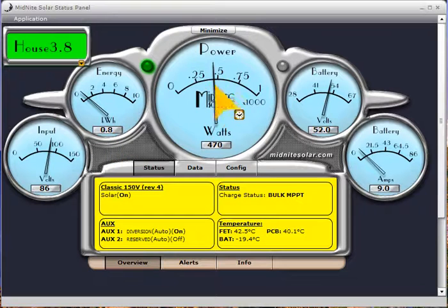And the next gauge is the power gauge. This is actually watts on the Classic itself, that single Classic. You can see it's doing 464 watts, and you'll notice that it goes to 1 kilowatt times 1,000, so 1,000 watts. This will actually scale. So if the sun was to come out right now and we bounced up to 3 kilowatts, this would go up to 3. This will auto scale upwards on the fly as needed to give you a better resolution.